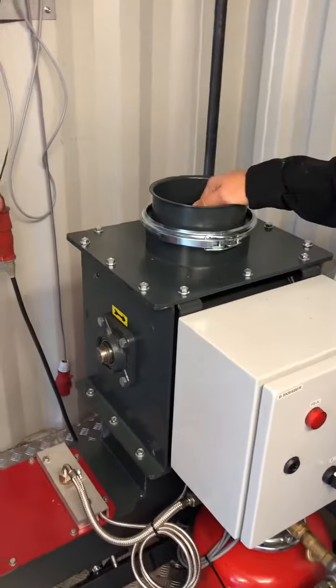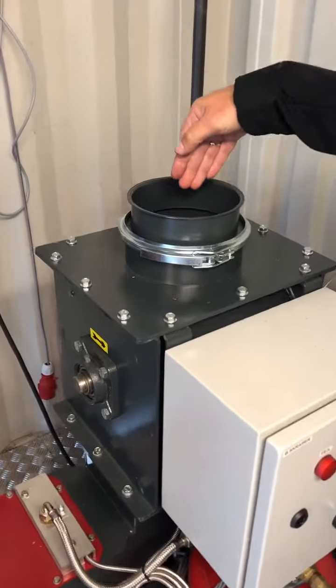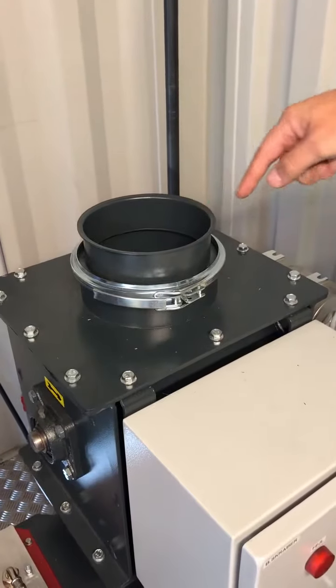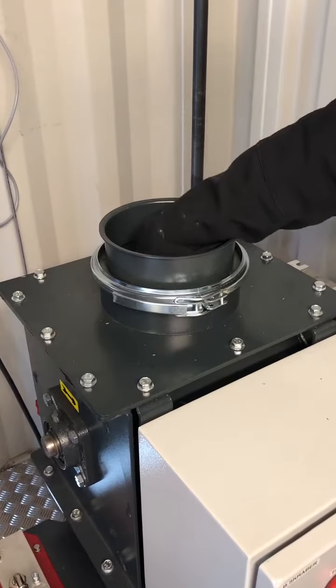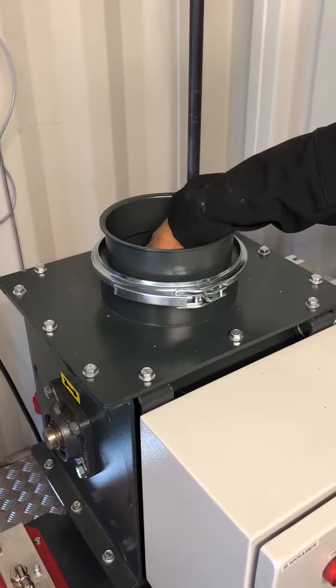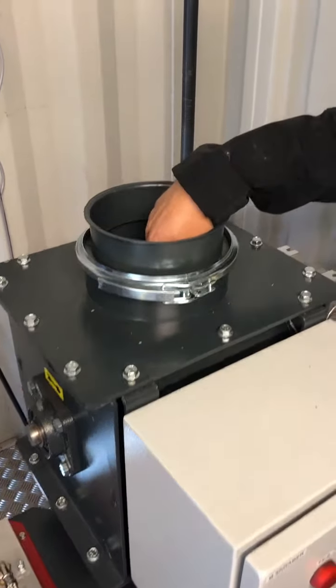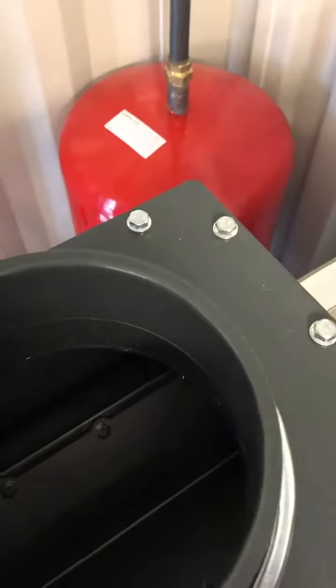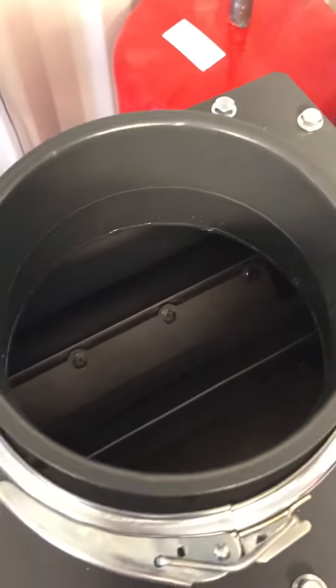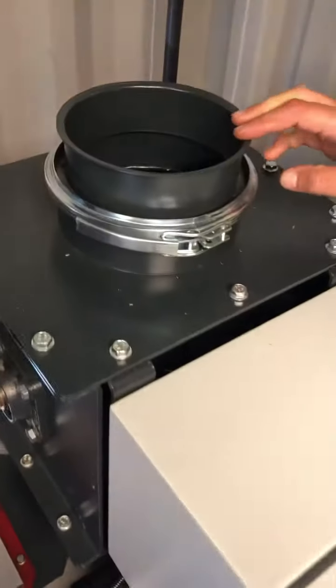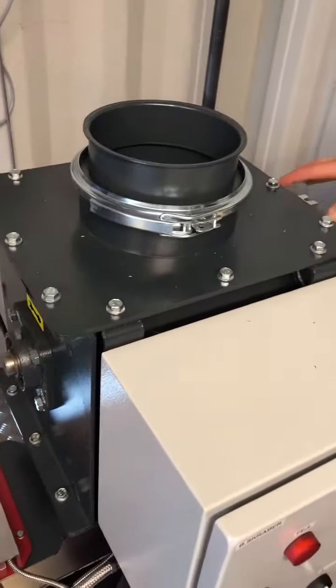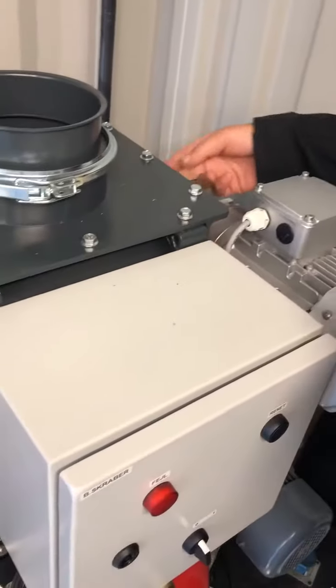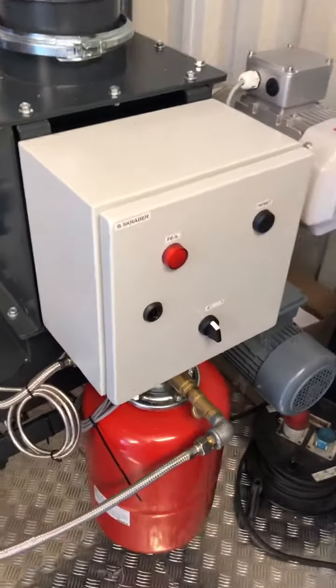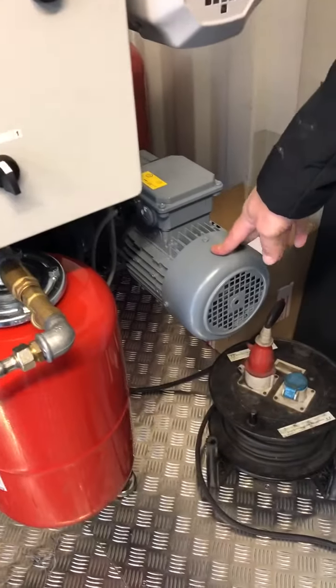This is the rotor valve, where we've got the 6 rubber valves, and always after some time you have to control that these rubber valves are okay, so it's airtight. To remove them, you can take the top plate off, but the easiest one is to take the gear out and the back plate. In here we have the motor, gear motor for the stoker auger, feeding the fuel into the burner tube.